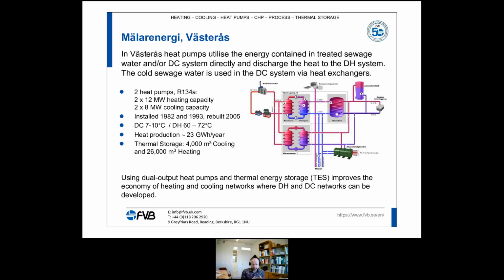And in order to make this operate well, we have two large thermal storages, one on the cooling side, 4,000 cubic meters, and one large one on the heating side, 26,000 cubic meters. And this plant has been in operation since the early 80s as well. And it was rebuilt in 2005, when both heat pumps were originally running on the sewage system, and in 2005 we connected one of them directly to the district cooling system. And that was really what I was going to present today.